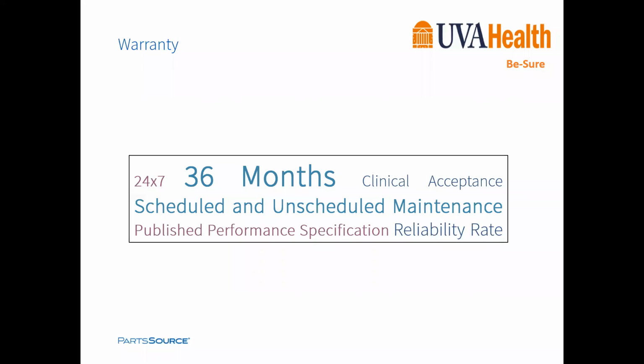At the very root, equipment must work in accordance with published specification data. That could be the operator's manual, that could be the service manual, and you typically will not find defects in the equipment in the operator's or service manual, and you can use that if you need to define the equipment as not working in accordance with performance specifications.